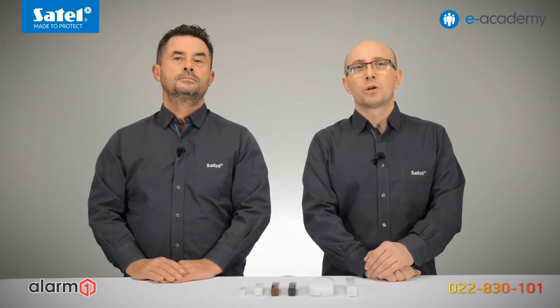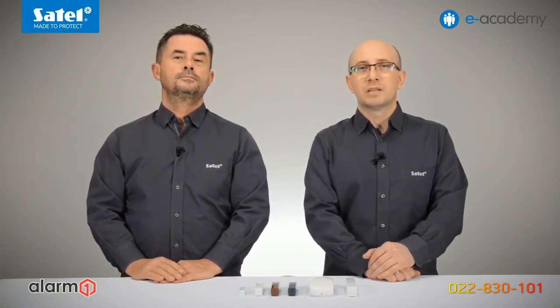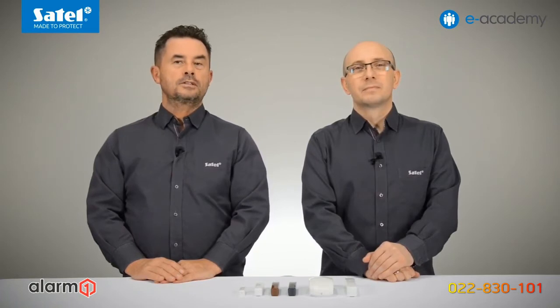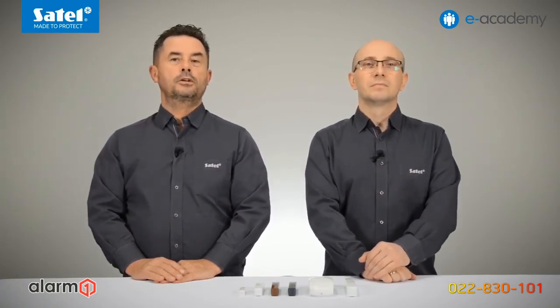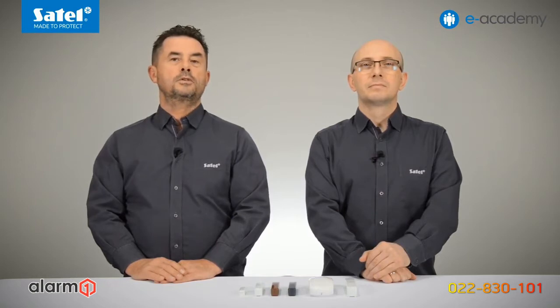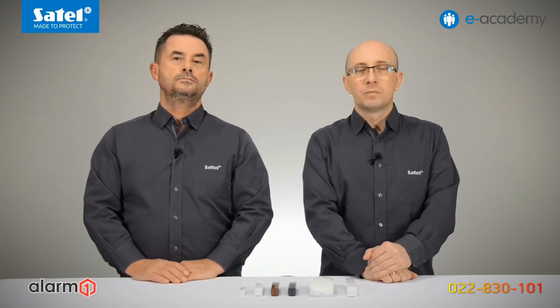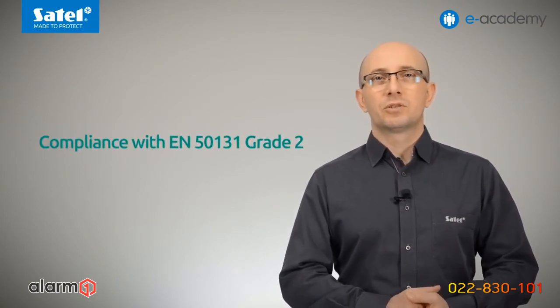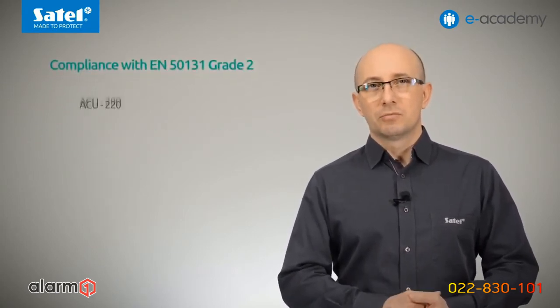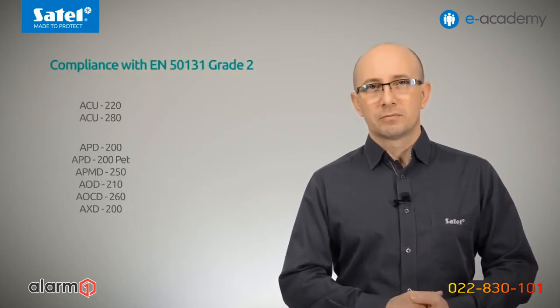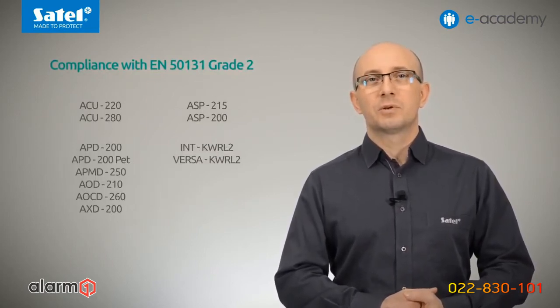New versions of the firmware for the ABAX 2 devices can be installed remotely. These devices are updated automatically after updating the system controller firmware. This process runs in the background and does not interrupt their normal work. The exception is the ASD250 wireless smoke detector. In its case, the option of automatic remote firmware update is not available. Devices of the ABAX 2 system meet the stringent requirements of EN 50131 for Grade 2. This applies to controllers, detectors, sirens, and keypads.